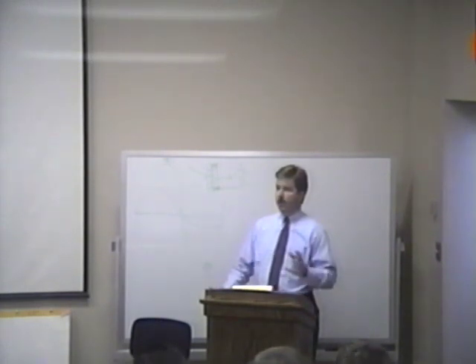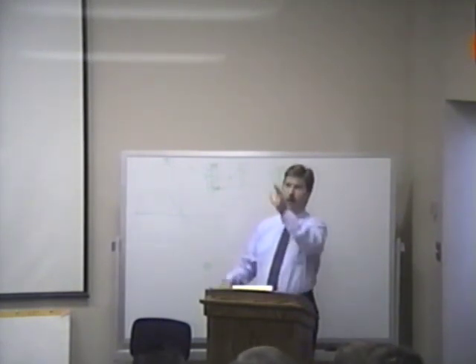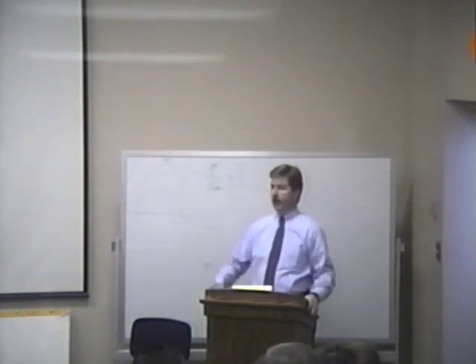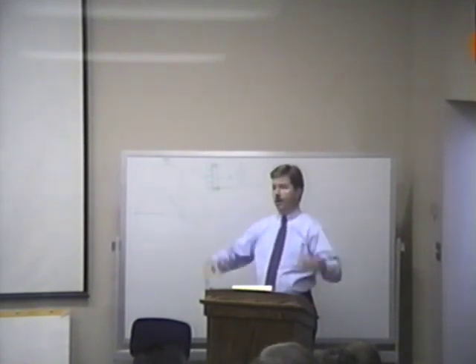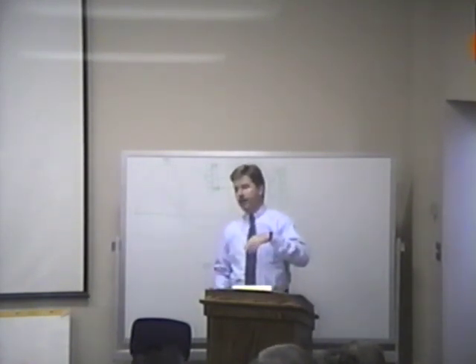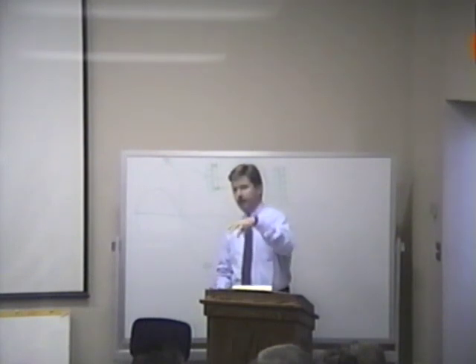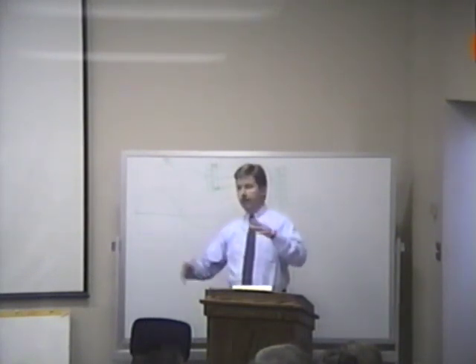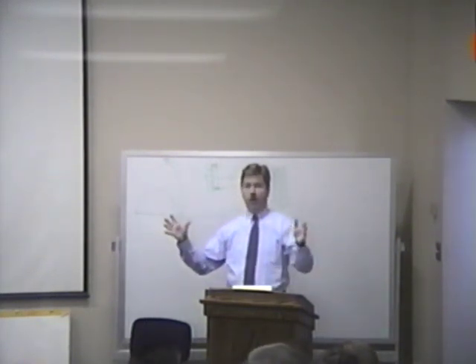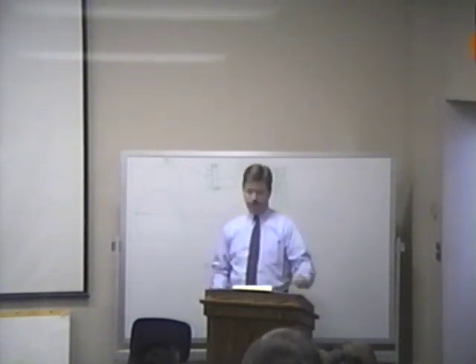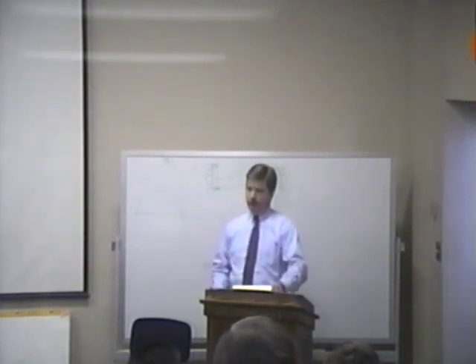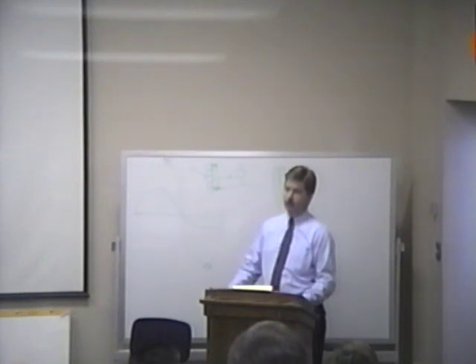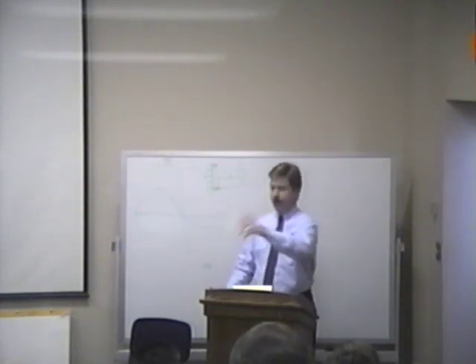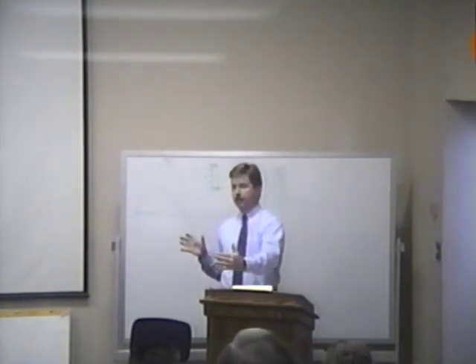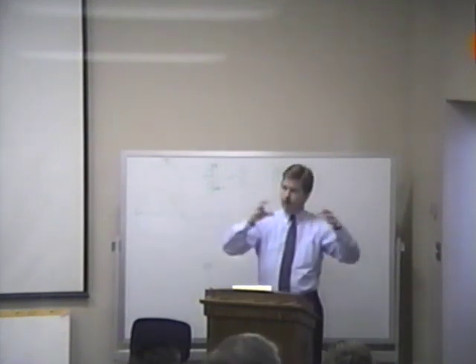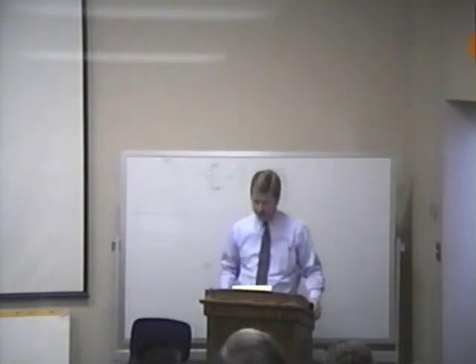And that's how many cubic feet of air per minute comes out each one of those registers. And again, that relates to the air changes per hour, and how many BTUs they calculate that you need, or not BTUs, but CFMs they need to provide so much cooling to this room. The room has a volume, and it has a requirement in terms of cooling, and they back into, well, how many CFMs of air at a certain degree temperature I need to provide to that room to satisfy that temperature. And then how do I balance the whole unit? So that's how those come into play.